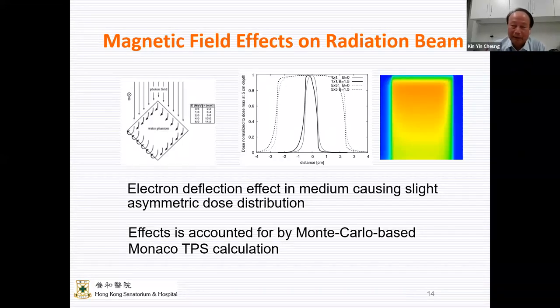On this diagram, you can see that the profile tends to shift to one side with the magnetic field. Without the magnetic field, it is nice and straight, as what you see in your linear accelerator. And on the right is the dose distribution in color of the radiation beam, so it's slightly tilted to one side. Such an effect is in fact taken into account by the planning computer system. The Monte Carlo algorithm corrects for such effect of the magnetic field on electron path, so we can calculate the dosimetry accurately.